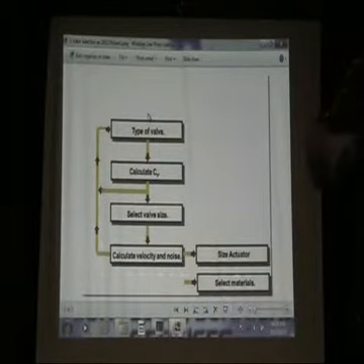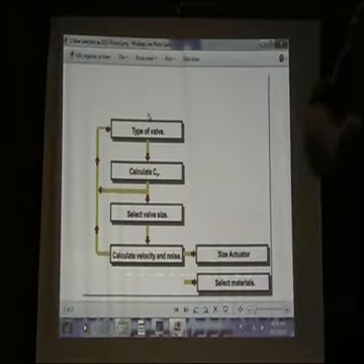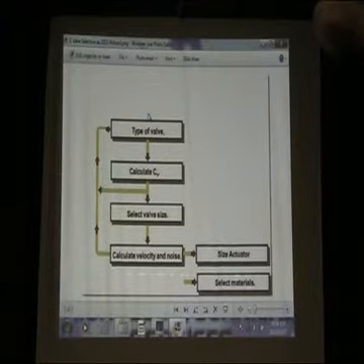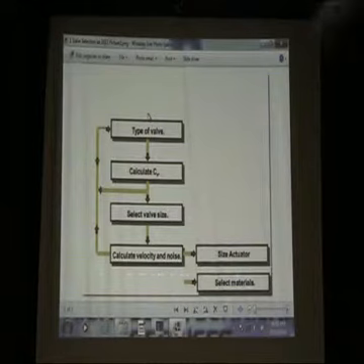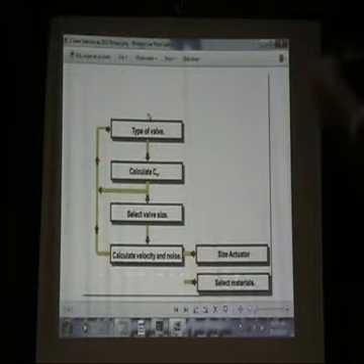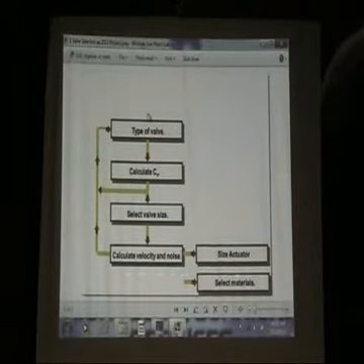Alright. While you've got it in that position, you can maybe just explain what's the biggest problem with butterflies. If it's in that position, how do you get it out of the line? There's one thing that the fitters still up until today do not realize. I've experienced in my 20 years in valves that when the fitters install these valves, they're supposed to close this thing and put it in the line.